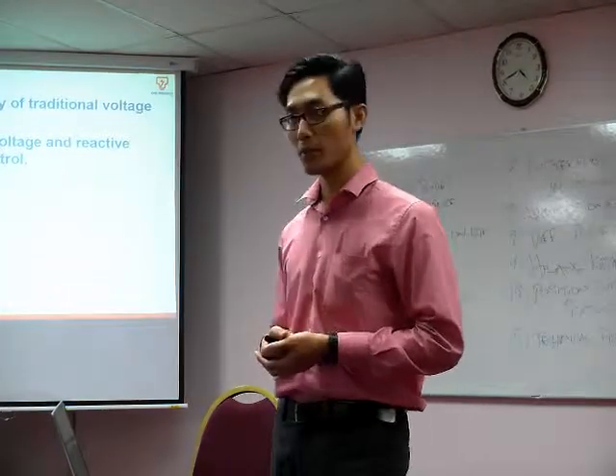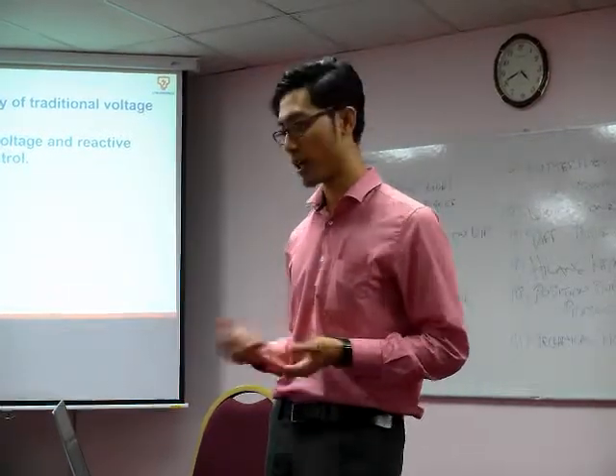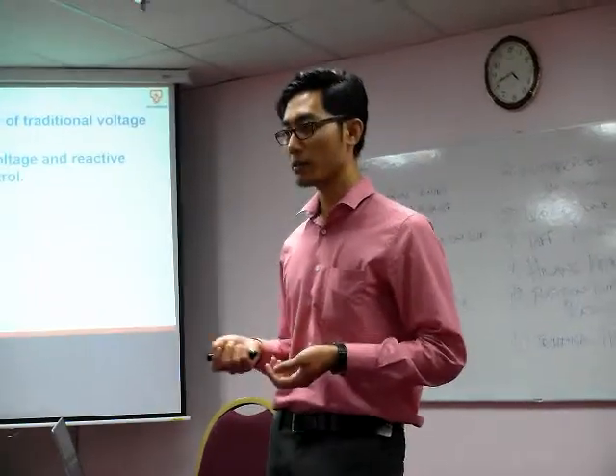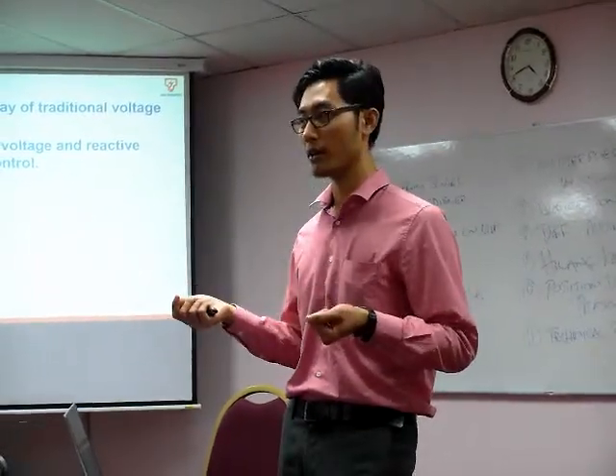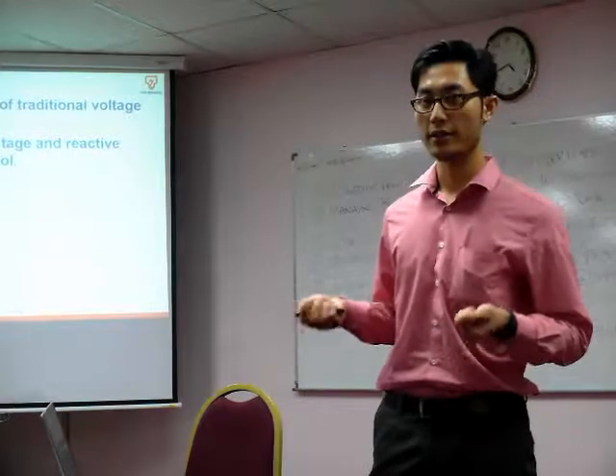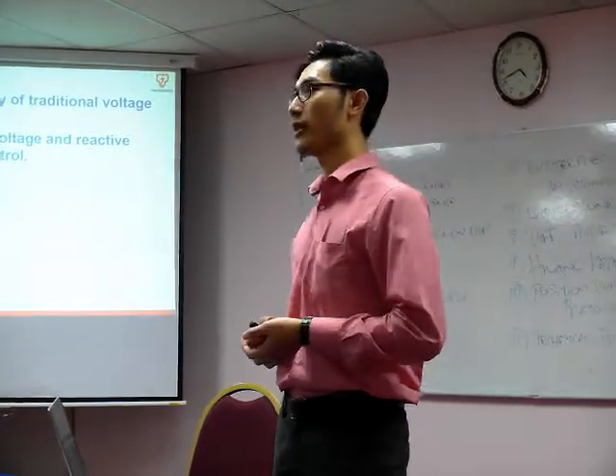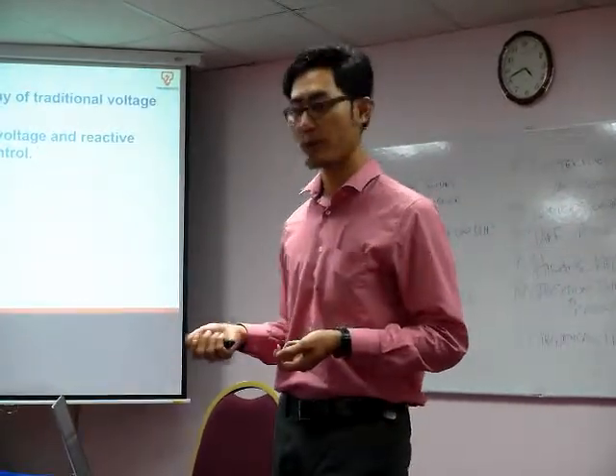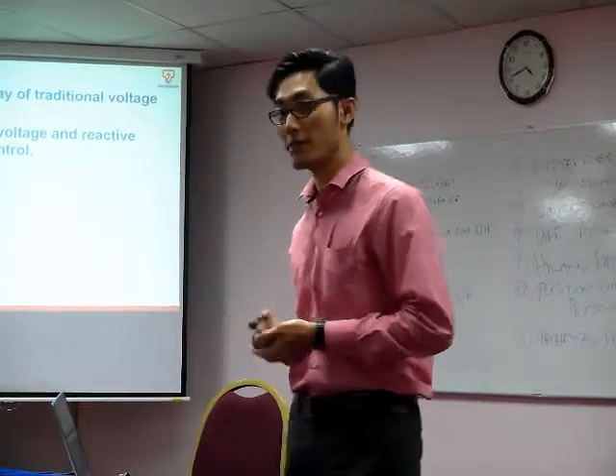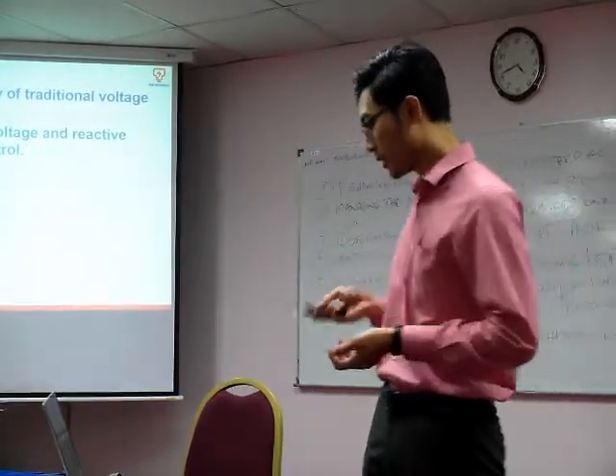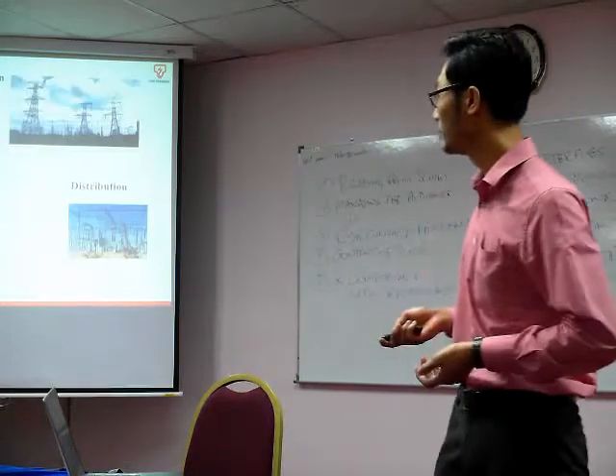You can control the voltage by controlling the reactive power. Reactive power sources can be found from the generator, from capacitor banks, reactors, and so on. You can also control it from the tap changer, the transformer tap changer. Okay, this is the situation.